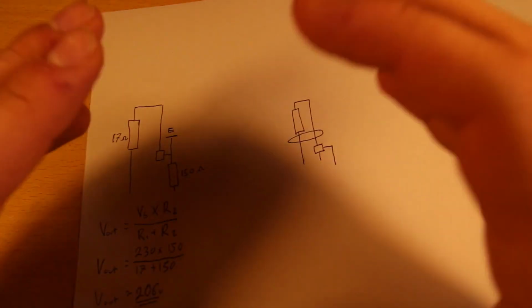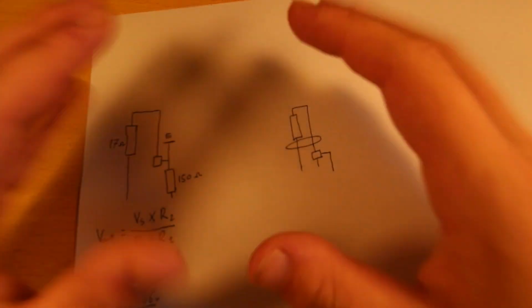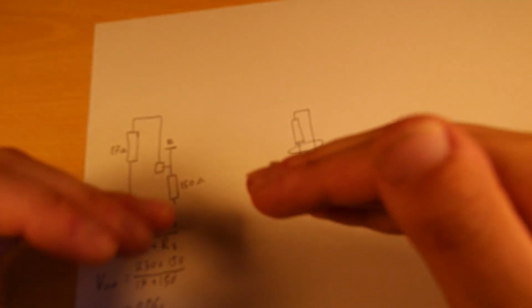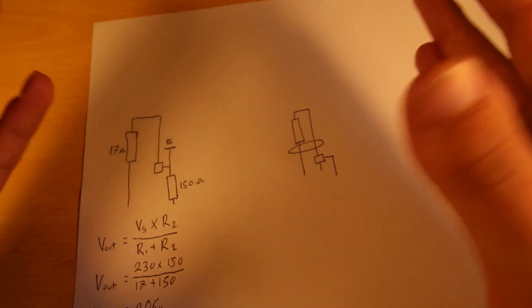So you need to check that the protective bonding conductor current is 0 and that the main earth current is low. It won't probably be 0, but it should be very, very low. If it is significant, sort of more than 30 or 40 milliamps, you should immediately stop work.